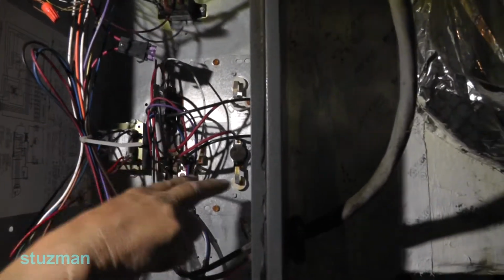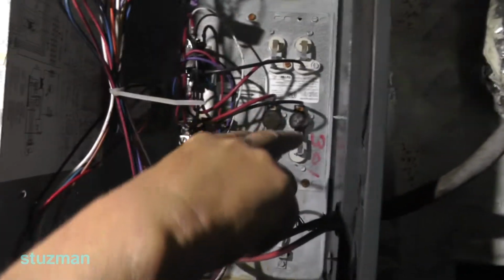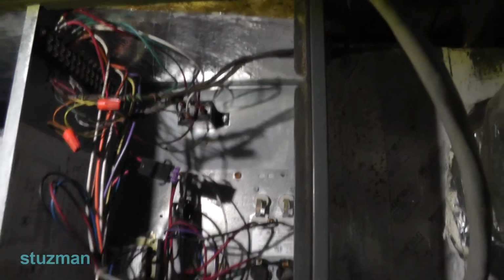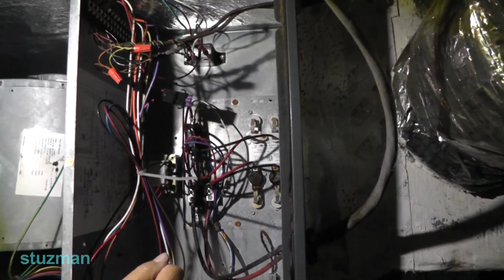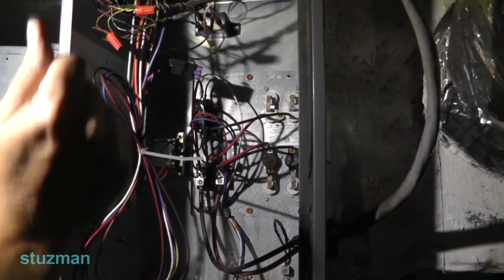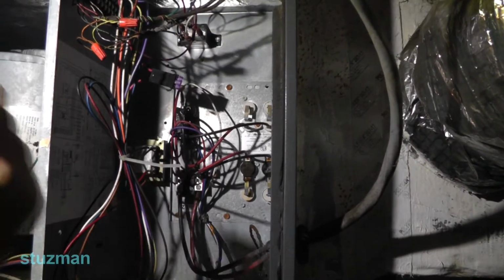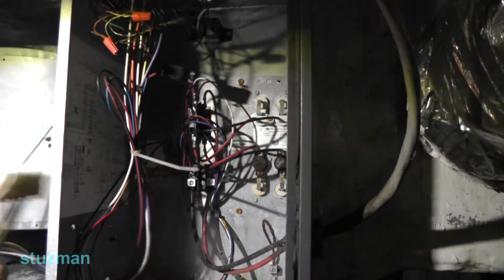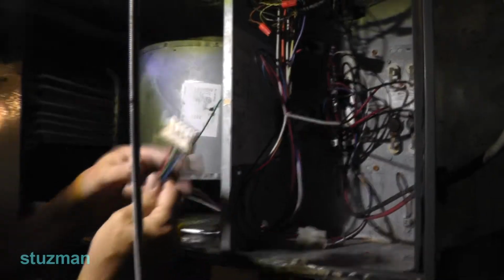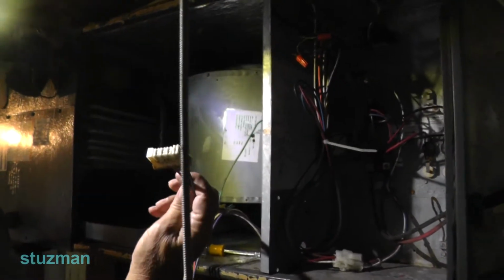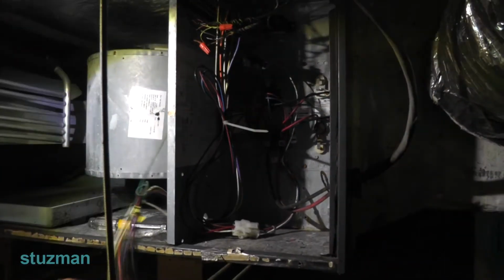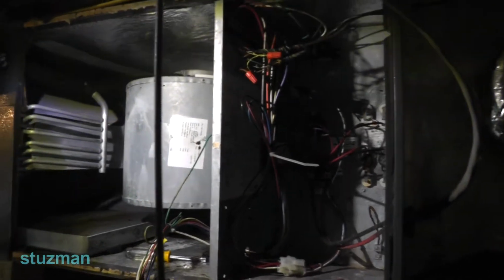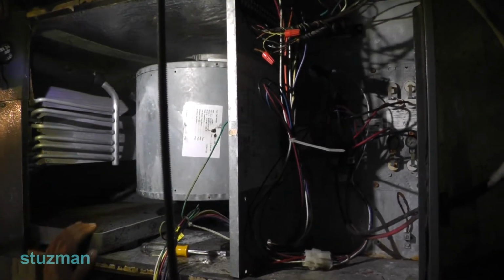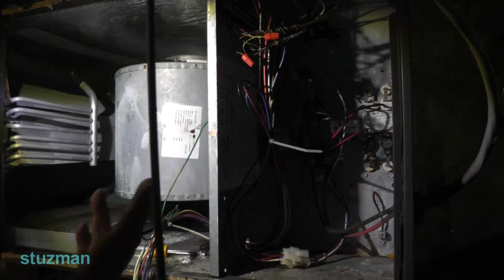Of course, you can see that we got our heater strips over here. Okay, up here we have a control relay. So basically when we go back up and turn the thermostat, we're going to turn on the fan so we can put our control volts out here, because right now we should have our 240 volts out here. Okay, so let's go up there, turn on the thermostat, come back down, check some volts, and see what we got.